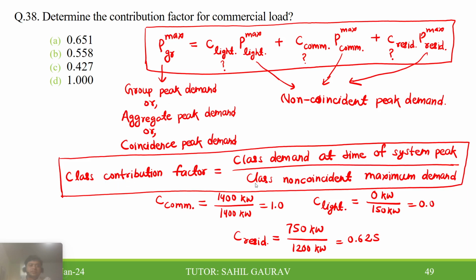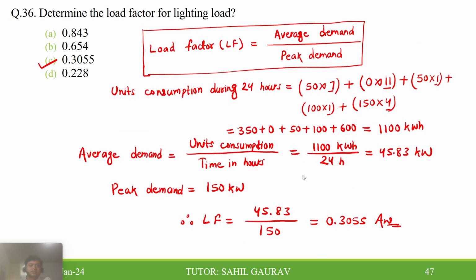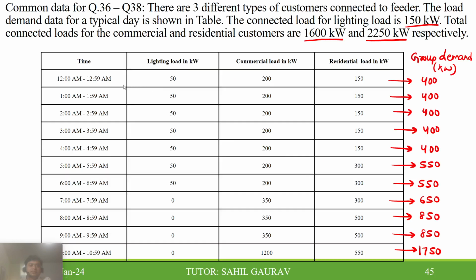The class contribution factor is the class demand at the time of system peak divided by the class non-coincidence maximum demand. Now first you have to find the system peak demand, that is the group peak demand. For finding peak demand you have to look into each hour. So we are calculating the group demand during each hour by summing up. So 50 plus 200 plus 150, that is 400 kilowatt, and this will give you 50 plus 200 plus 150, 400 kilowatt, respectively.